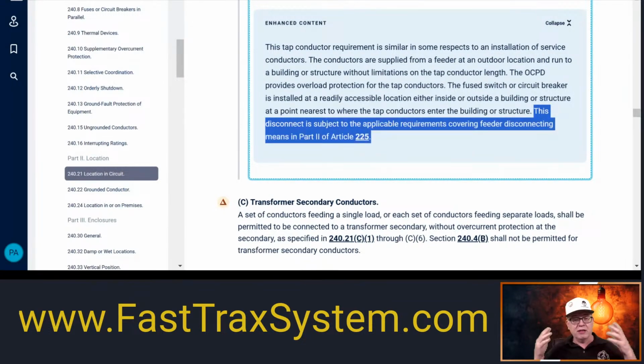Absolutely. So remember, it could be a situation where it's a feeder tap outside and it's actually feeding a whole different occupancy. It might be feeding one building, and it might have a 2-hour separation, and that feeder tap might be feeding another building. Well, at that point, all the feeder rules, all the disconnecting rules in Article 225, will come into play. So again, you have to be careful about all those types of things.